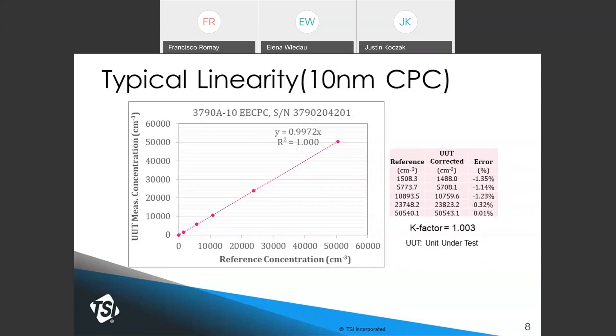For a 10-nanometer CPC — the TSI 3790A-10 — a typical calibration curve shows the concentration range extended from 10,000 all the way to 50,000 particles per cc. The correlation is perfectly linear with R-squared of 1 and a slope of 0.997, giving a K factor of nearly 1. This calibration is done against an electrometer, because using a CPC as reference would require an ultra-fine CPC with a very small cut point.